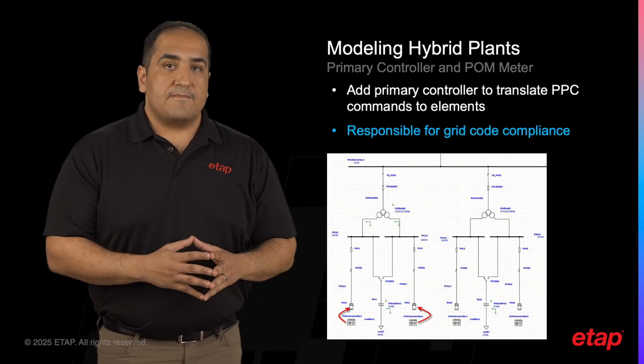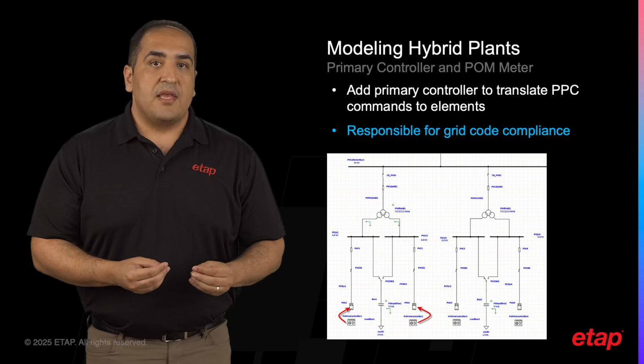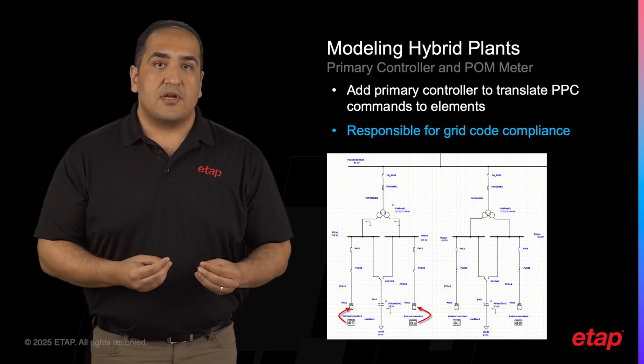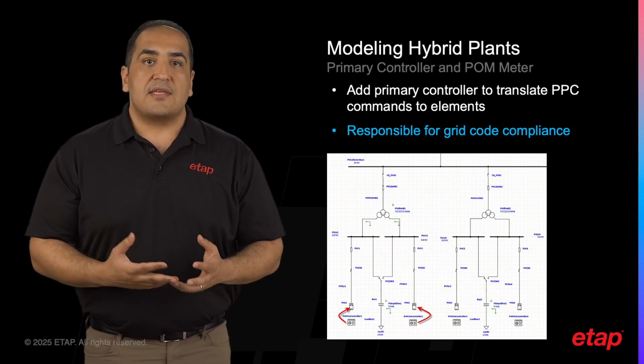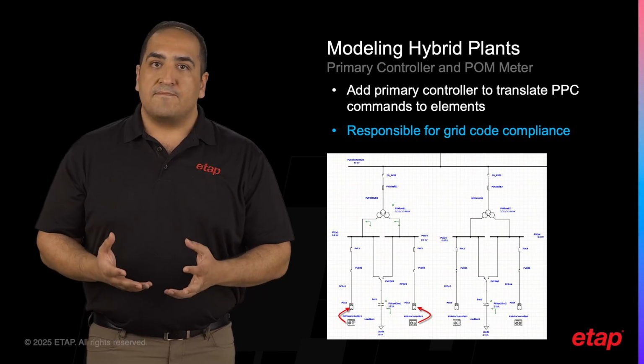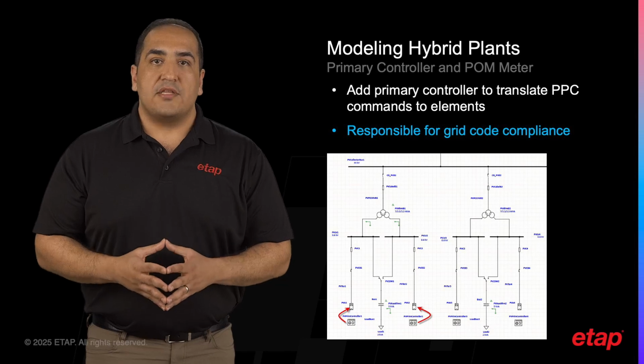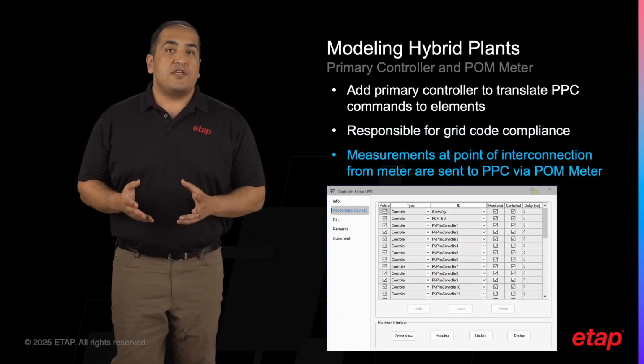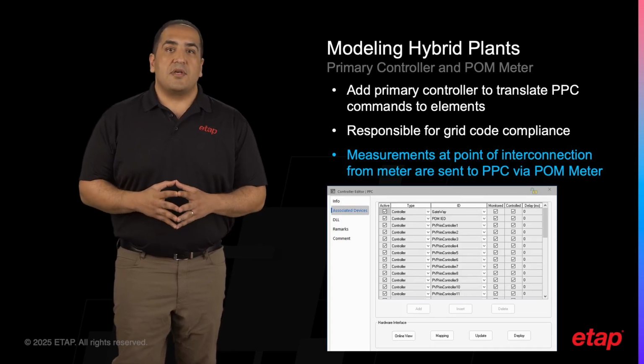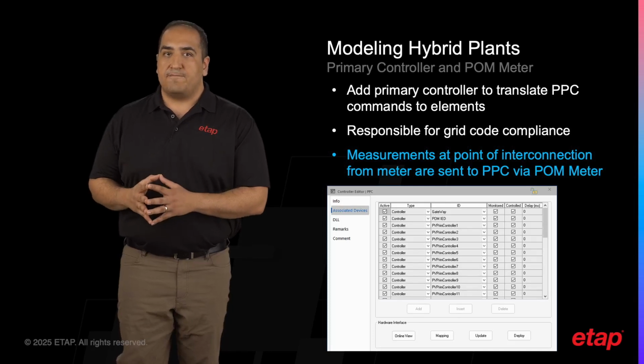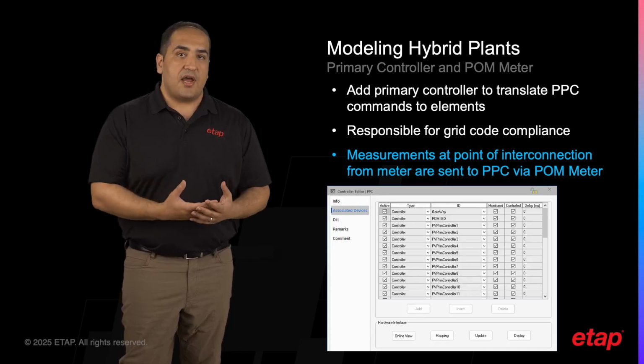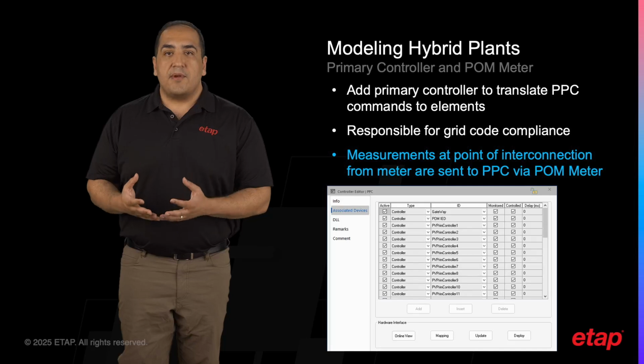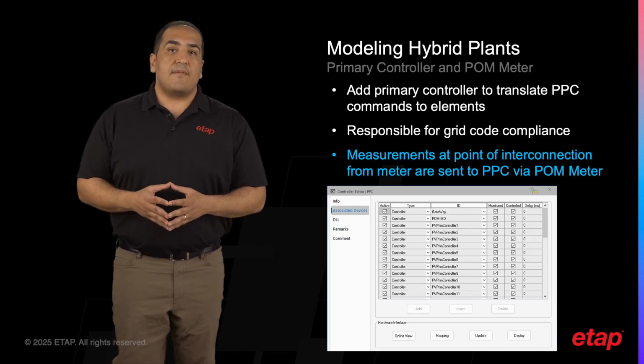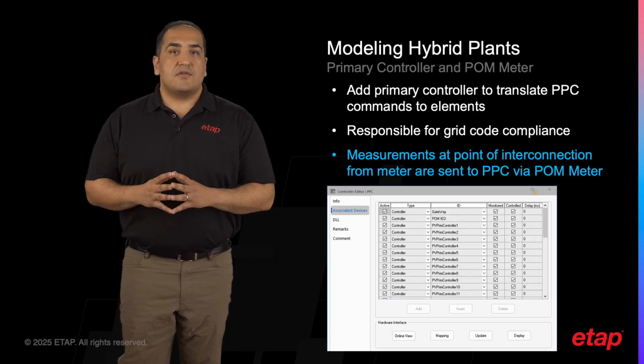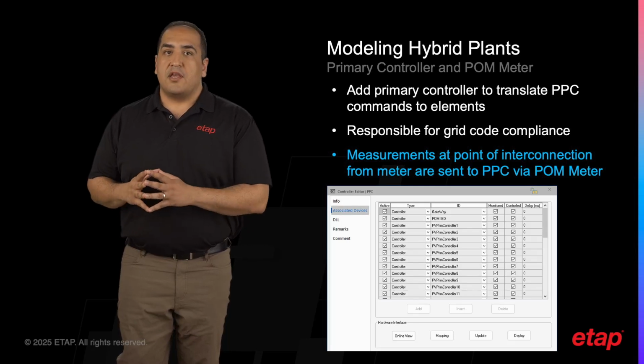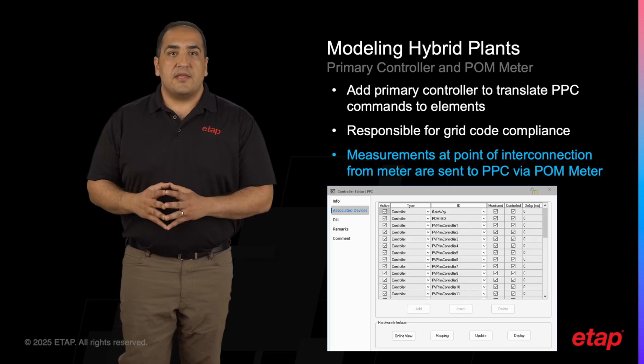Once these controllers are integrated, the next step is to incorporate EPPC into the project. This involves associating the primary and meter controllers with the EPPC and granting it access to the settings and operational parameters of all relevant electrical components. At this stage, the system is nearly ready for simulation and software-in-the-loop testing. However, before initiating these tests, the settings within the EPPC need to be configured according to the specific requirements of the power plant project. This customization could involve setting up sequential dispatch for asset management in one project or configuring renewable smoothing function in another. The flexibility and depth of ETAP modeling capabilities makes it possible to tailor each project to its unique operational needs, ensuring that EPPC can perform its role with precision and efficiency.